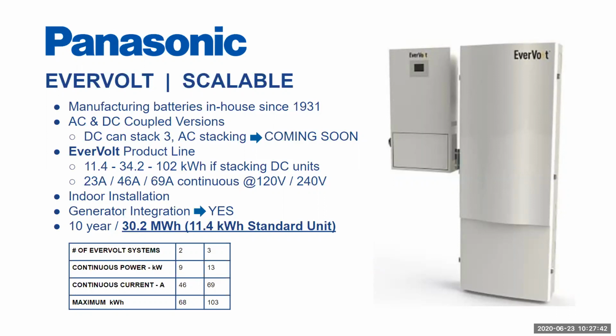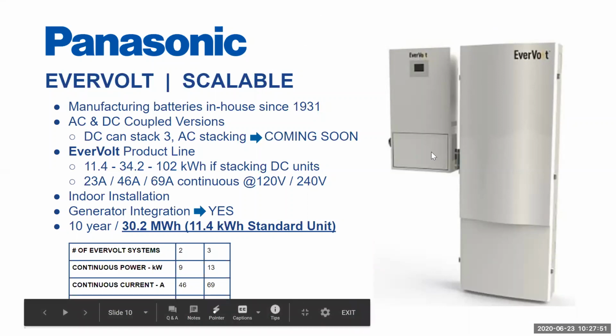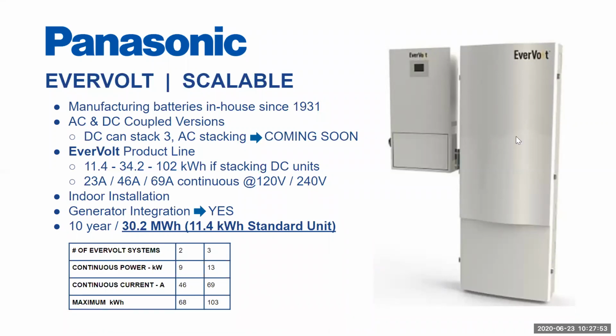Something I want to mention is DC stacking. In this case, we can stack up to 3, meaning you could do 3 of this whole system. So you'd have 3 inverters, and let's say in our case, 3 battery stacks on a given singular critical load panel. And this is really important to note. So if you have an EV charger, let's say, that you really want to back up, you can increase your power output by adding multiple inverters on your single critical load panel.